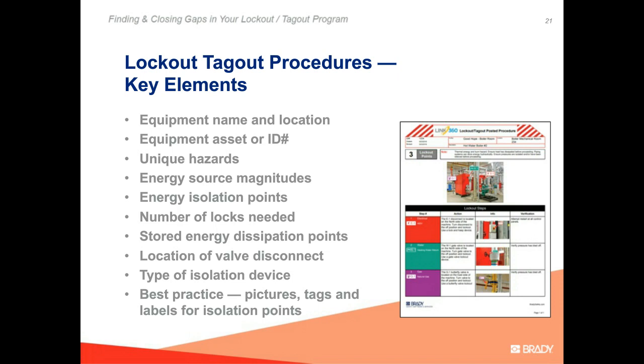The total number of locks and isolation points for the equipment need to be located, identified, and devices recommended to bring that isolation point completely closed so that it cannot be reopened. The verification that the energy source is isolated and stored pressures are removed, at gauges or by dump valves, needs to be included to achieve a zero energy state.